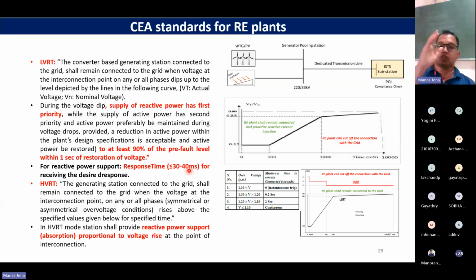You supply the VAR using something called a K factor, which you can understand if you refer to 2800. Using the K factor, we decide how much the VAR should be. Once you decide the VAR requirement, if your inverter still has some capacity, you can give the remaining component to active power. But the reactive power should be given priority. Then, once the fault is cleared, which is very important, what is mandated? At least 90% of the pre-fault level the inverter should reach within 1 second of the restoration of voltage.